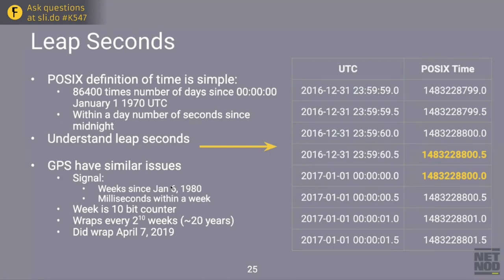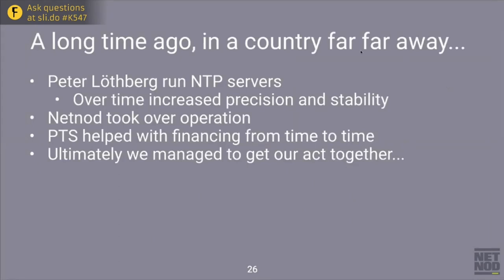GPS has also similar issues to POSIX, because inside the GPS signal one week is a 10-bit counter. That means the GPS signal wraps every 2^10 weeks — about 20 years. There was a wrap on April 7, 2019, and yes, there was some equipment that went down because it had hard-coded which 20-year epoch it was going to work in. The intention from the manufacturer was not that it would survive in production across April 7, 2019. It will now take another 19 years before we have another wrap in the week counter in GPS.